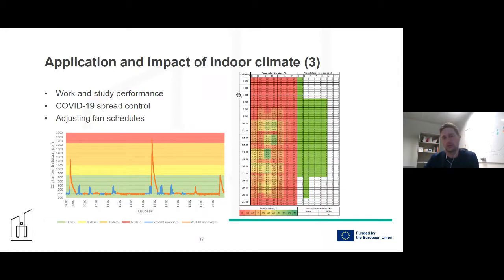We can also do this with indoor climate data. Here you see CO2 values measured in an auditorium. When you see these small fluctuations, that means the classroom was in use. Blue values correspond to the time when the fans were on, and orange values correspond to the time when the ventilation system was shut off.